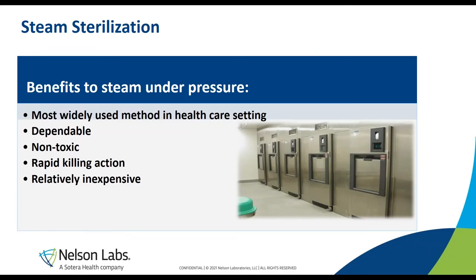Steam sterilization — specifically saturated steam — has definite benefits. It is the most widely used method in healthcare settings, very dependable, well-understood, non-toxic, with a rapid killing action, and relatively inexpensive. It's a great option for a device that can handle high heat.